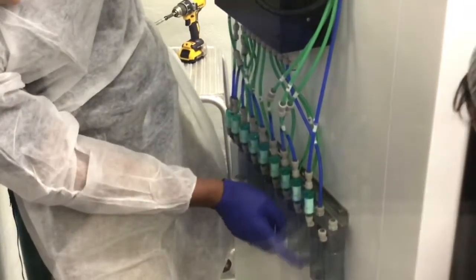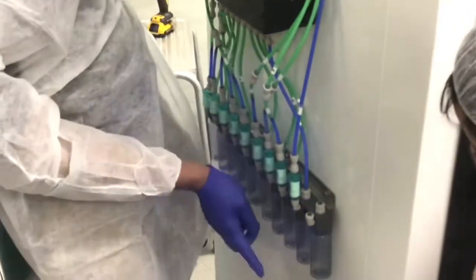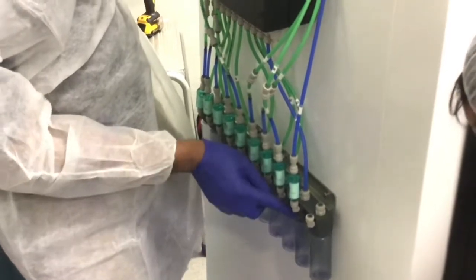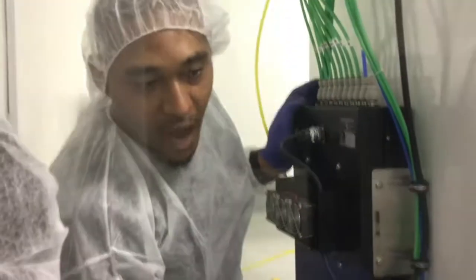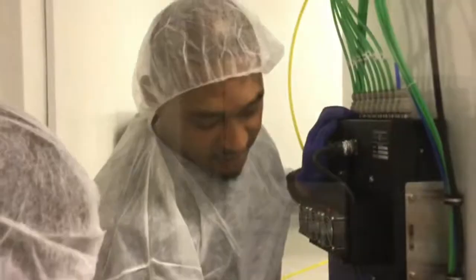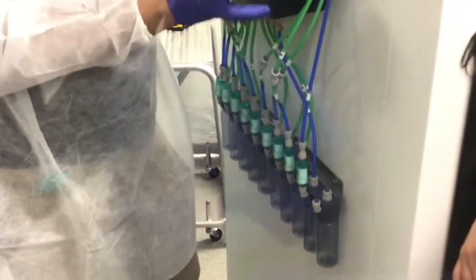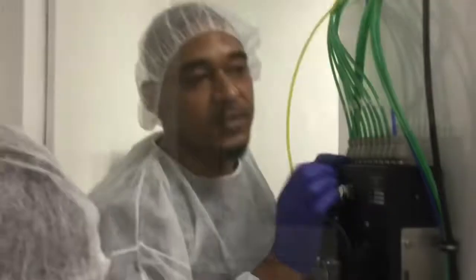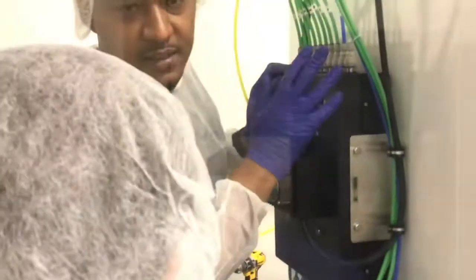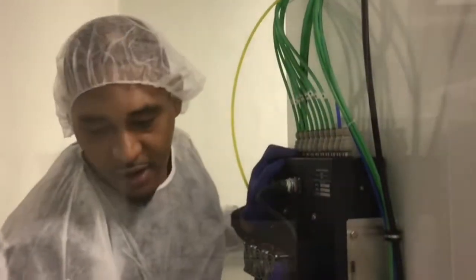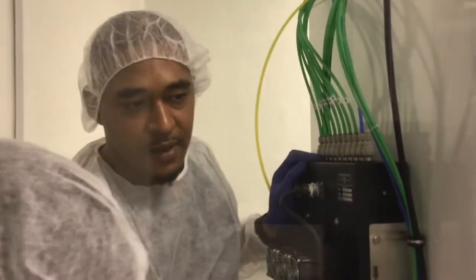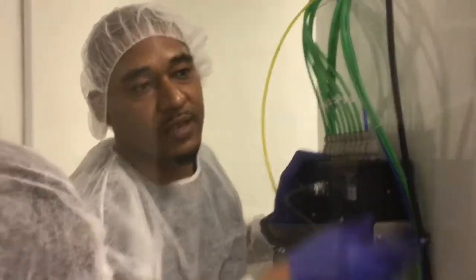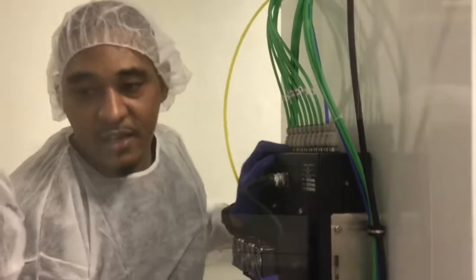Oh, you guys can see, yeah, a drop of water. So it removes water from the air and sends it to the UGC, the gas conditioner. It removes most of the water, I'd say about 90%, and the other 10% is taken care of by the dry wipe. I wish it could do 100% so we wouldn't need the dry wipe, but that's not possible at this point.